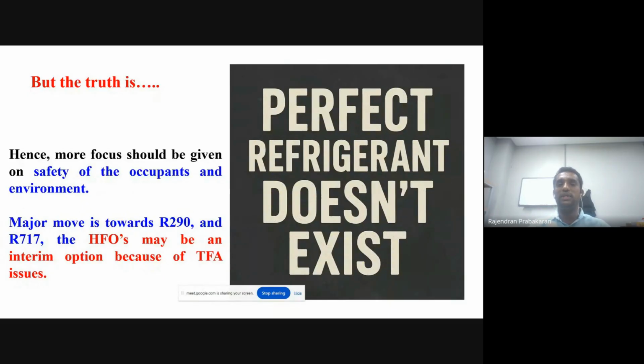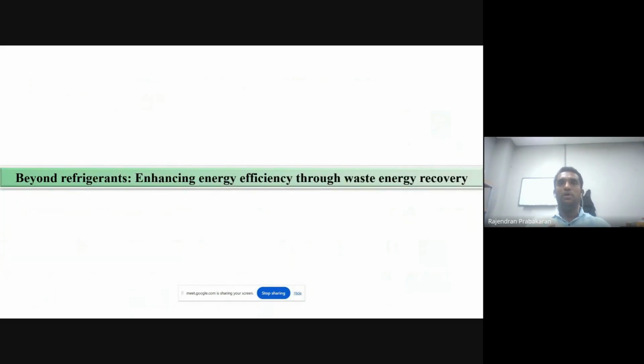So the focus should now be given to the safety of the occupants and the environment rather than the performance, because all these refrigerants are good in performance. So we need to focus on occupants and the environment. Hence, the major move of low GWP refrigerant is towards R290 and R717. So this alternate refrigerant study clearly indicates we can use low GWP refrigerants, even natural refrigerants, but we need to take care of safety. So this is one part, refrigerant.